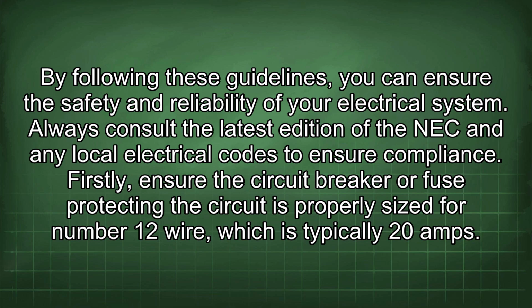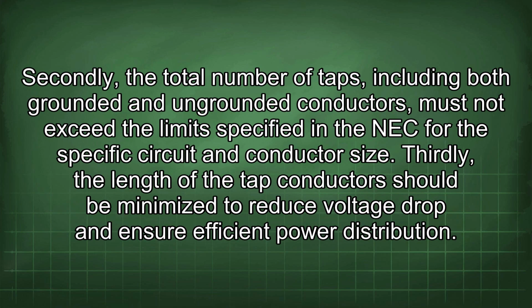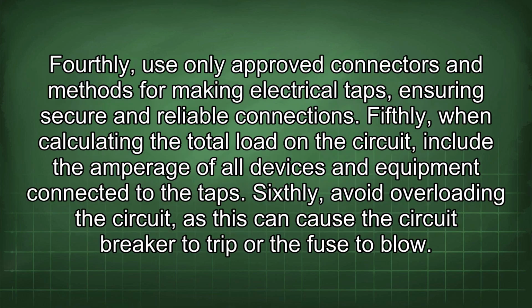Firstly, ensure the circuit breaker or fuse protecting the circuit is properly sized for number 12 wire, which is typically 20 amps. Secondly, the total number of taps, including both grounded and ungrounded conductors, must not exceed the limits specified in the NEC for the specific circuit and conductor size. Thirdly, the length of the tap conductor should be minimized to reduce voltage drop and ensure efficient power distribution. Fourthly, use only approved connectors and methods for making electrical taps, ensuring secure and reliable connections.